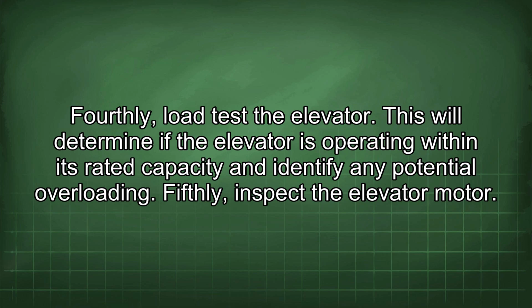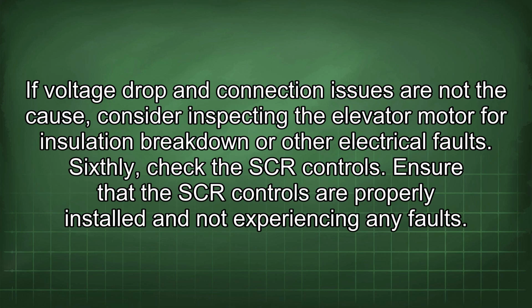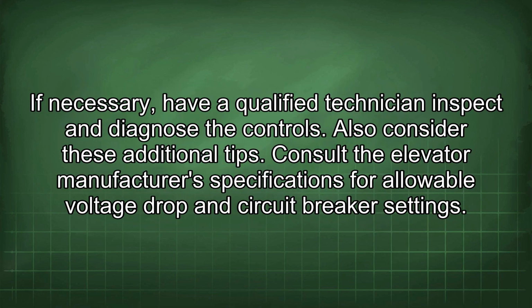Fifthly, inspect the elevator motor. If voltage drop and connection issues are not the cause, consider inspecting the elevator motor for insulation breakdown or other electrical faults. Sixthly, check the SCR controls. Ensure that the SCR controls are properly installed and not experiencing any faults. If necessary, have a qualified technician inspect and diagnose the controls.